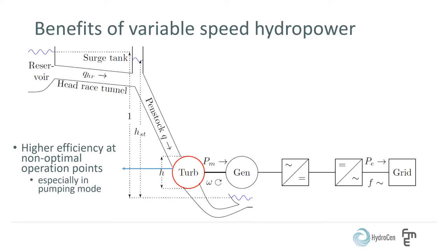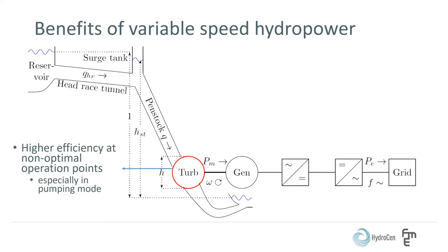The other main advantage is that the grid connected converters are able to deliver auxiliary services to the grid. Since the rotational speed can vary, the rotational energy or the kinetic energy of the turbine and generator can be utilized to deliver virtual inertia, also called synthetic inertia, by controlling the active power output to the grid. The speed and precision of the voltage control can also be improved by controlling the reactive power output.